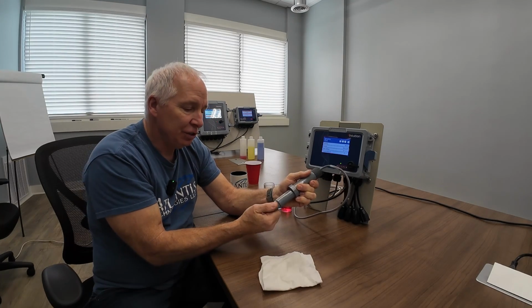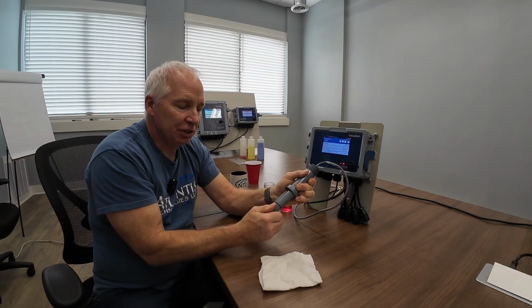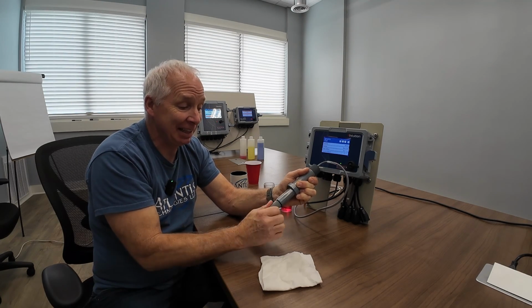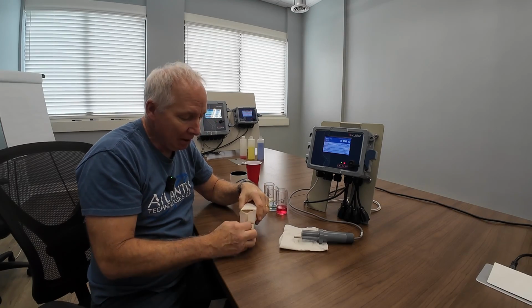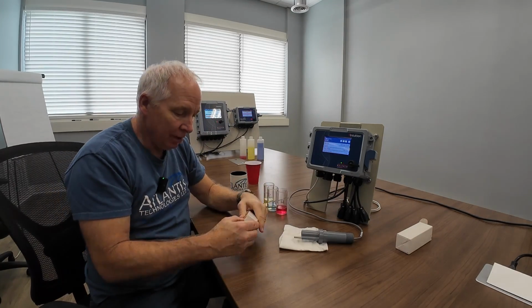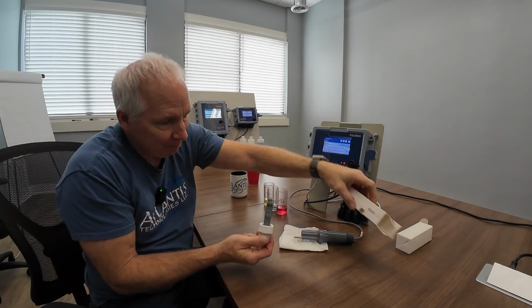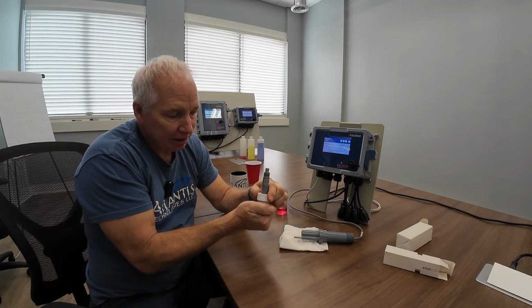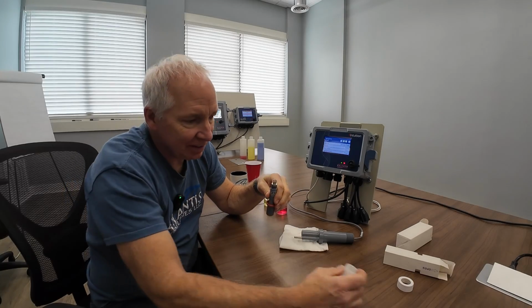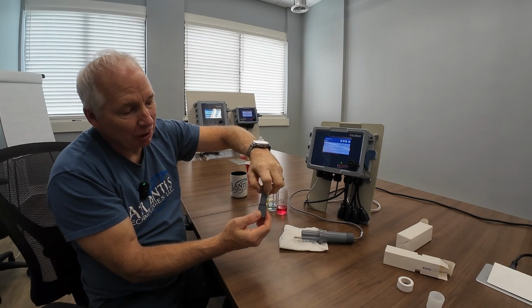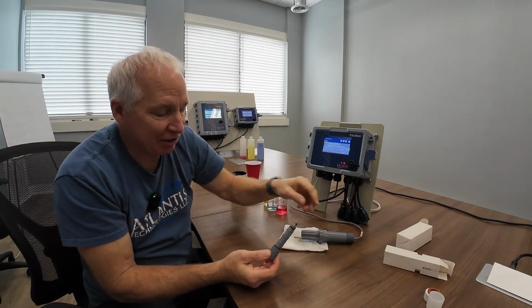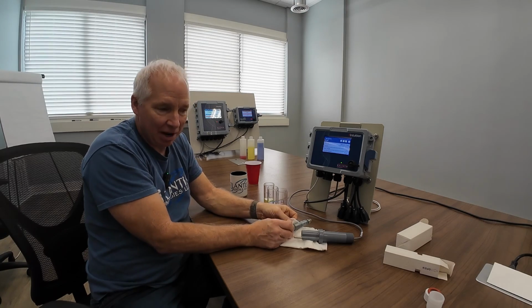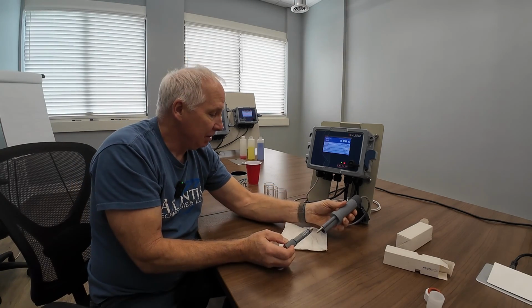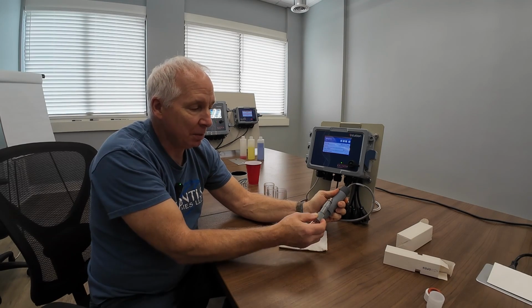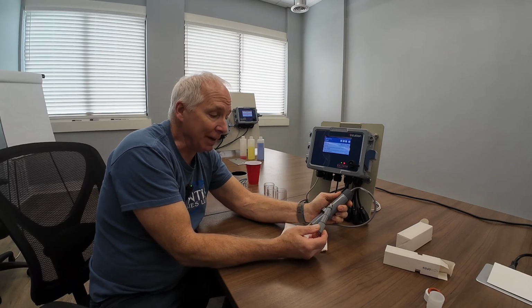If you need a new cartridge, don't use any tools. You should be able to do this just with your fingers. Hopefully somebody didn't really tighten this thing in before. All right, so I'm going to put a new electrode in this, so I get one out of my box here. They come in a storage buffer in a little vial like this. You unscrew the cap, you take this out, and there's a storage O-ring. We want to get rid of that. So we pull that off. Do not install that on the probe with that red O-ring because it will not work. You won't get a tight seal and you'll get a leak. And if you get any water up in this housing, there is an amplifier in it and you will ruin it.